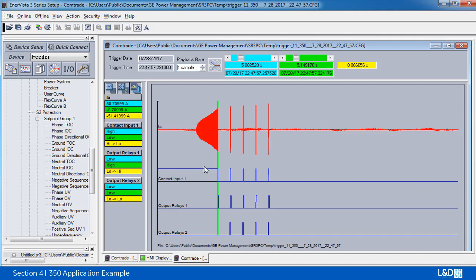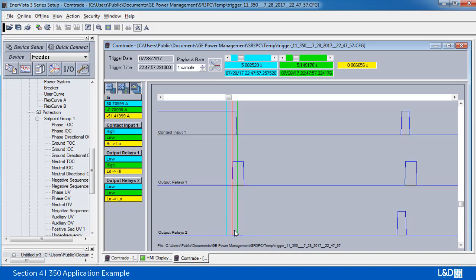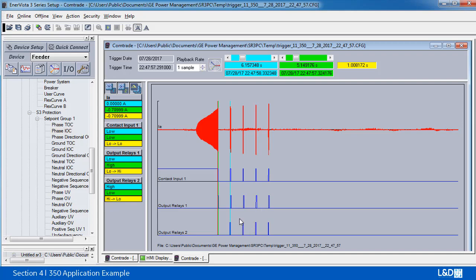And contact input 1 is a 52A. Initially it's closed. Then when the relay operates, that's the trip relay. It trips, starting the auto-reclose, initiates the auto-reclose. If I zoom in on shot 1, I totally got 4 shots, but if I just look at shot 1, I can see that from the breaker initiation to the auto-reclose, relay 2 is the close relay. I can see that the dead time of this shot 1 is 1.008 seconds. So that's the setting of our 1 second. And we have this same 1 second for the whole 4 shots.